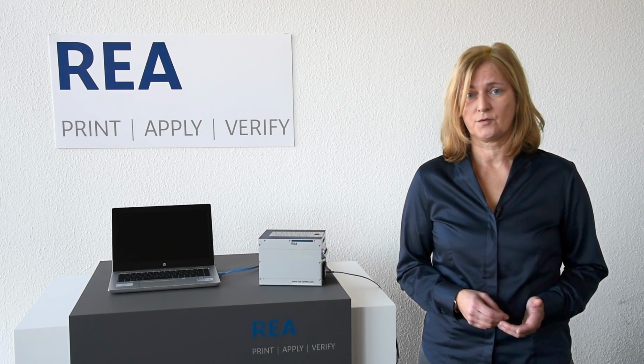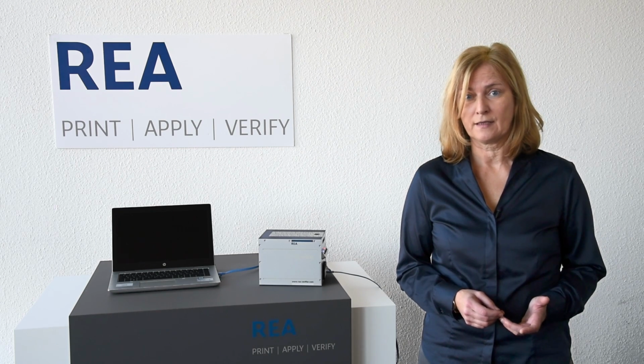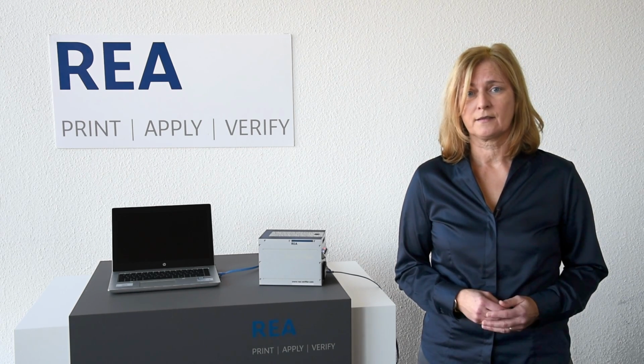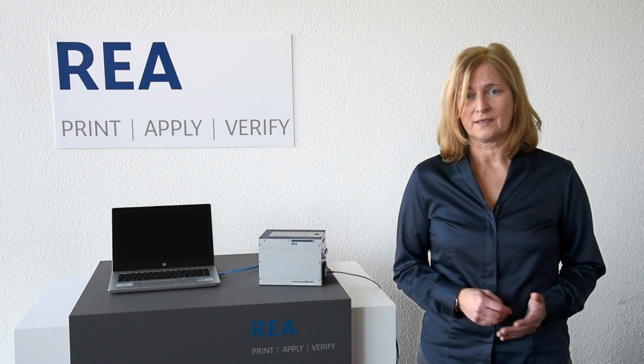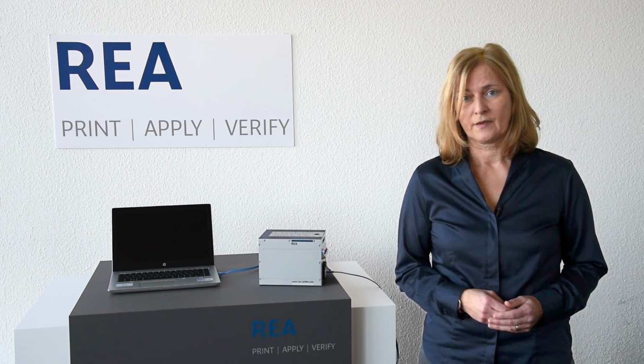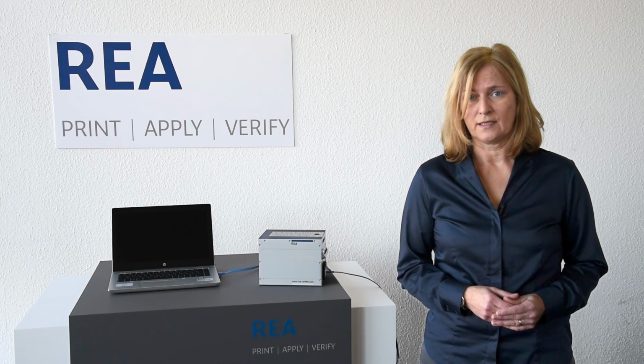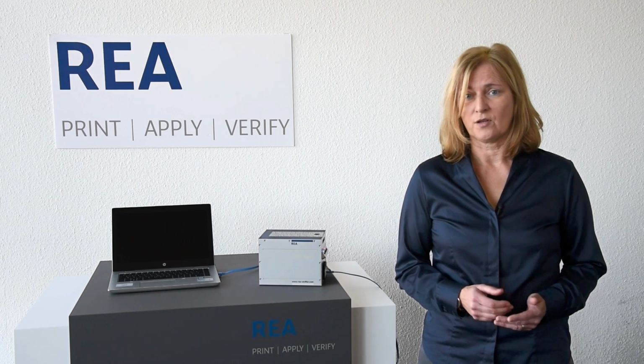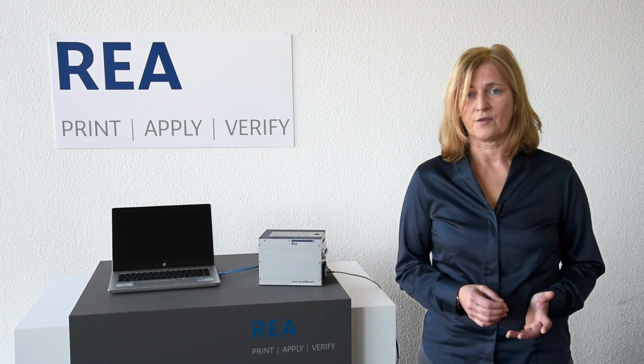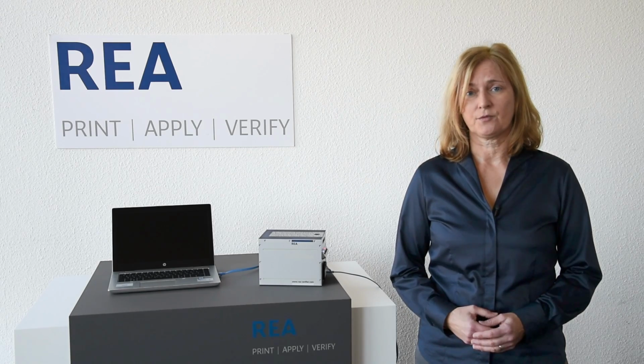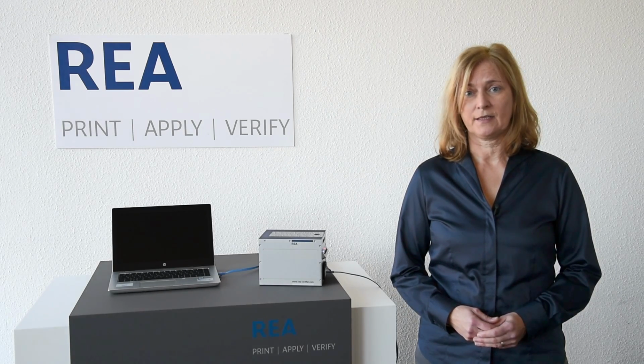Verifiers are subject to tolerances in measuring accuracy that are specified in standards. To check the accuracy of your device, the calibration must be performed regularly. We recommend monthly calibration. Please watch also our tutorial calibration for this procedure. In order to obtain reproducible measurement results, some more points must be taken into account when performing a measurement.